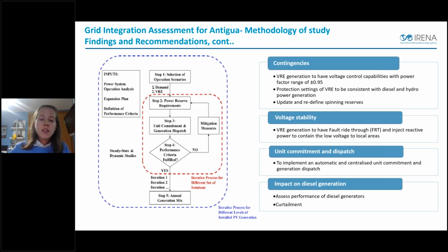As said before, operational scenarios were chosen which depict the system at its most vulnerable, such as maximum VRE and peak demand, and maximum VRE and minimum demand. Following this, the required power reserves, such as frequency regulation reserve and contingency reserves, are calculated, considering the variability of VRE power generation. The impact of variable renewable generation is analyzed in each operation scenario on the stability of the system, as well as line overloading and frequency deviation. If there are issues, mitigation measures are implemented and the new network configuration is again simulated to assess for further issues. If no more problems exist, the annual generation mix is calculated, considering the variable renewable generation and the demand profile.